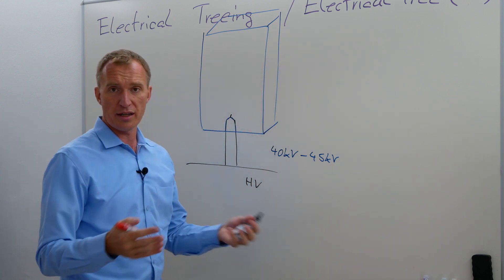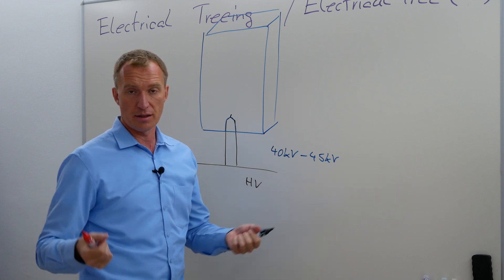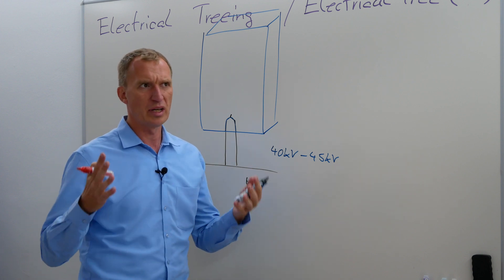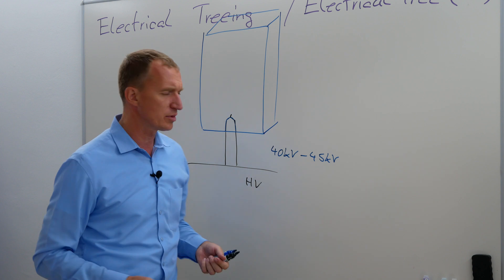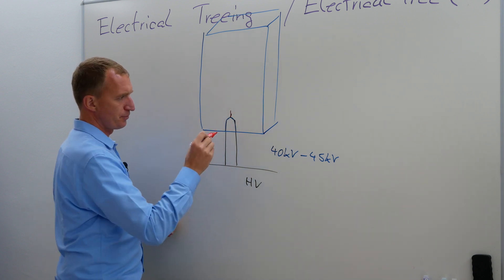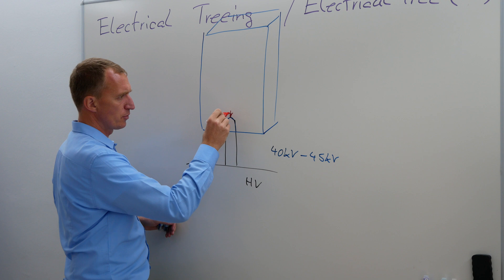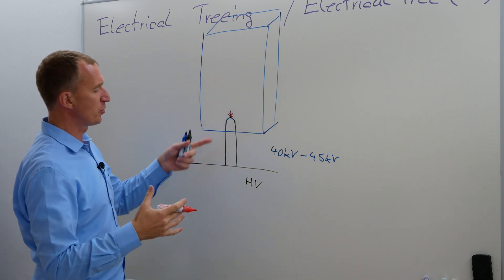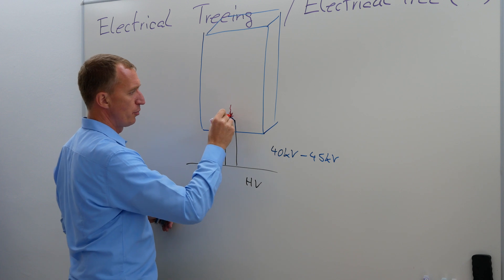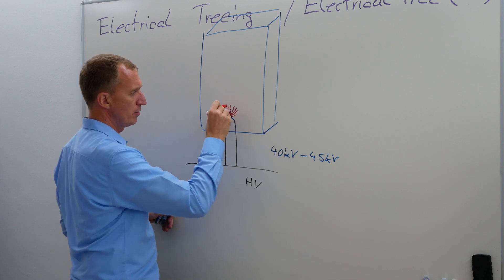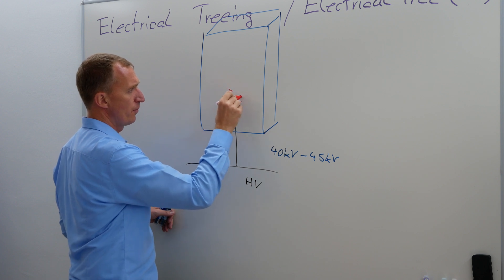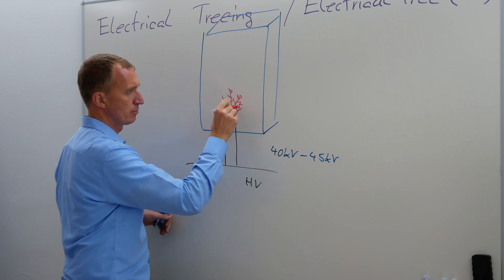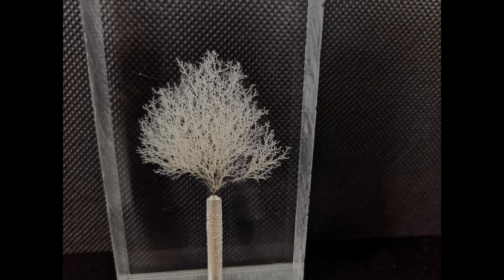Well, we were able to check the creation of this electrical tree took a couple of days, maybe a week or something like that. So what happens is, you got the first discharge here and the first one here and here and here. And as it kept growing, they're getting bigger and longer. And all of them have these little branches, as you can see in this photo again.